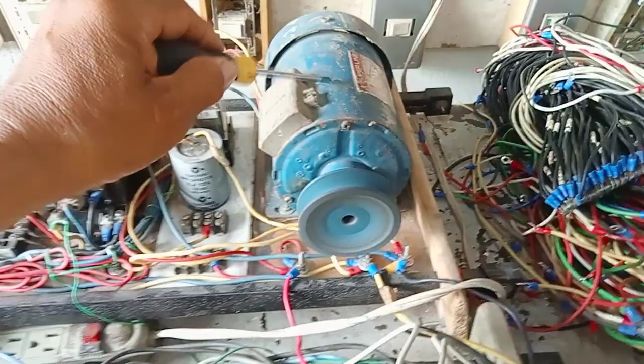I've tested this, guys - vulcanizing machine motors, 3-phase, I can operate in single phase. Vulcanizing motors are just an example. So I connected it from 3-phase to single phase, and as you observe, the motor is running normally. This one runs on single-phase supply, while this one runs on 3-phase supply. Did you get it?